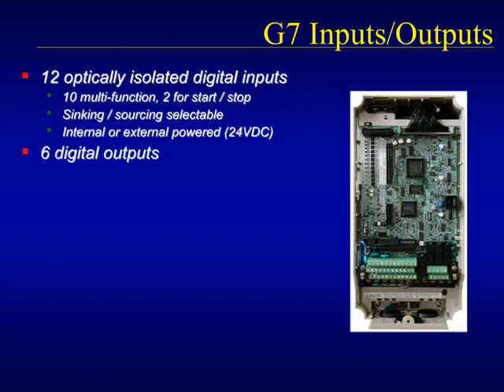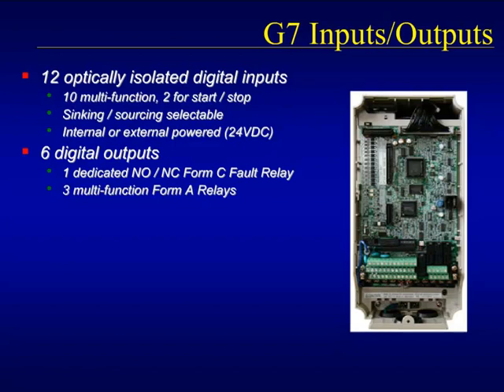The drive comes standard with 6 digital outputs, with more than half of the digital outputs on the G7 actually being relay outputs. The dedicated fault relay is a normally open, normally closed Form C relay. 3 other Form A relays have their functions set by the user. 2 extra open collector outputs are also user configurable.